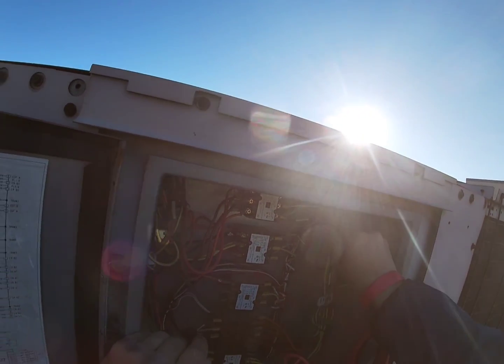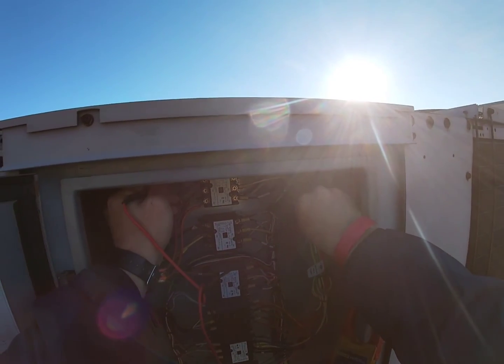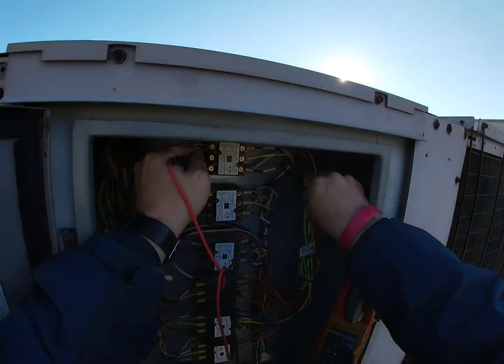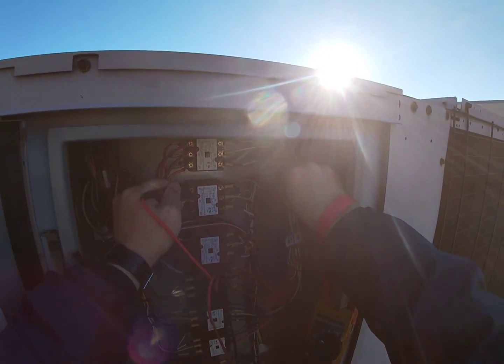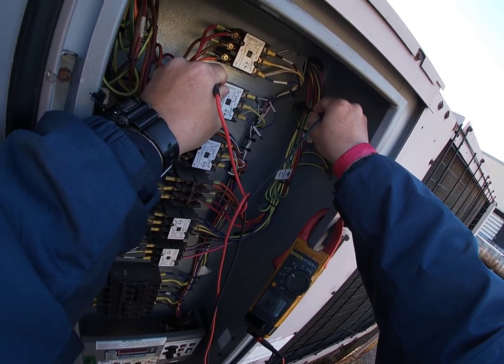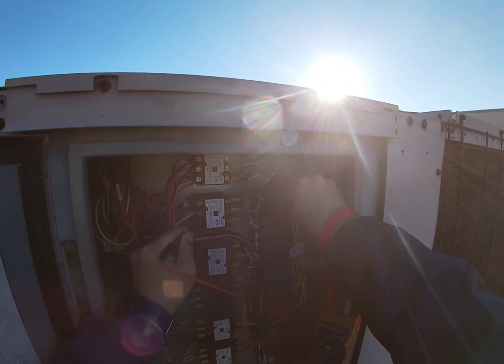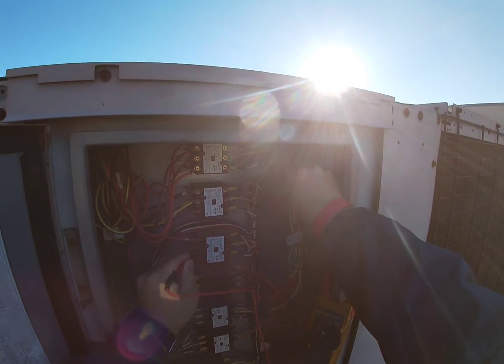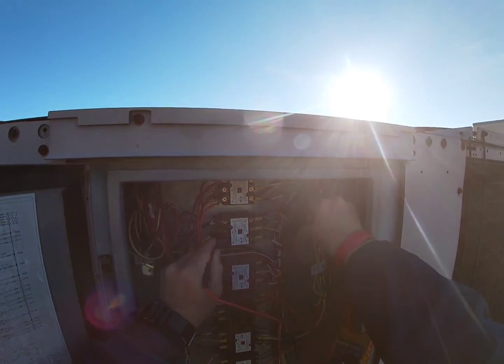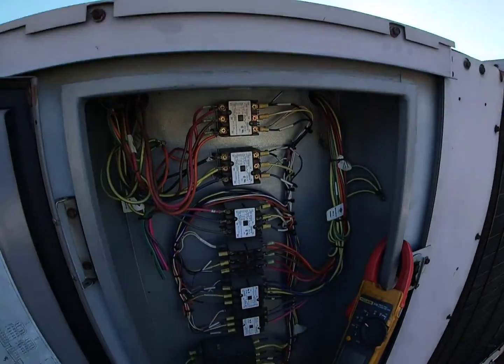So resistance, let's just go straight to ground first. So I'm checking 2 motors, 2 legs on 2 different motors here. See, we got, yeah, so one of these motors is grounded. Yep, all 3 phases. Here you're good, here you're good, and here you're good. So the issue is over here, one of those condenser fan motors.